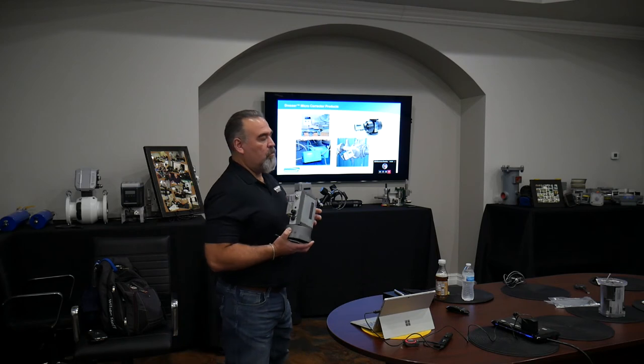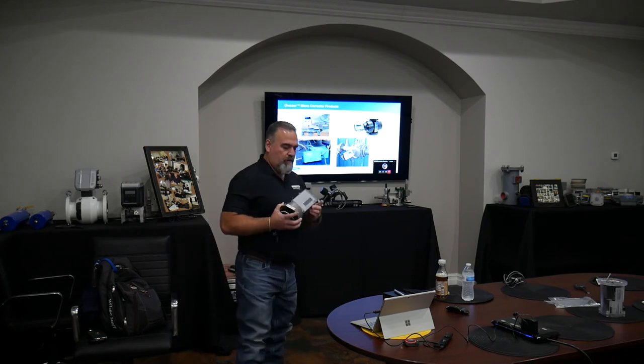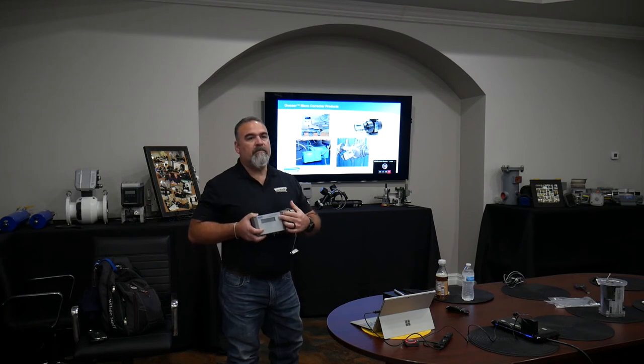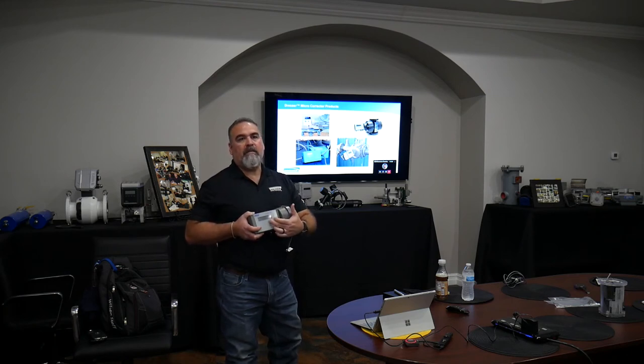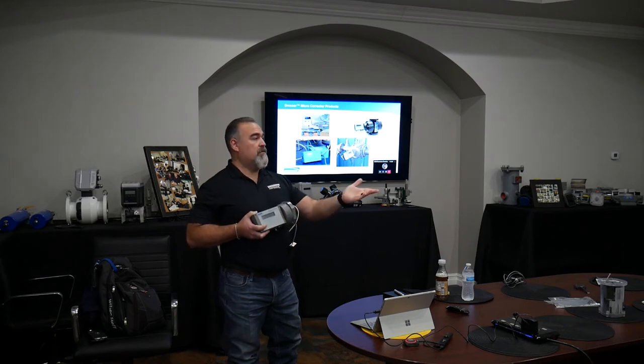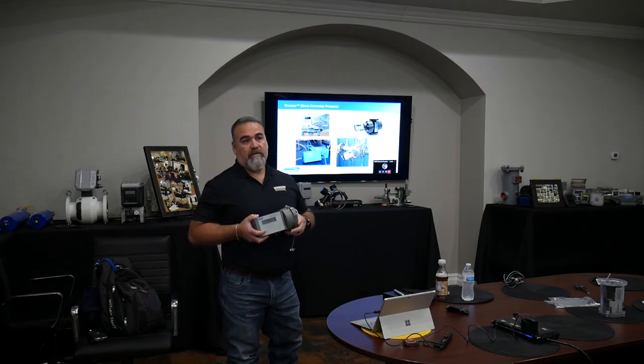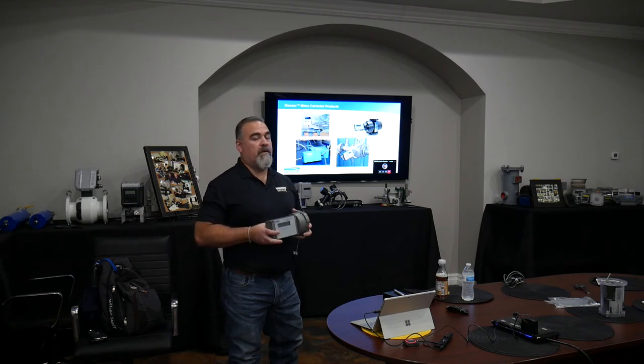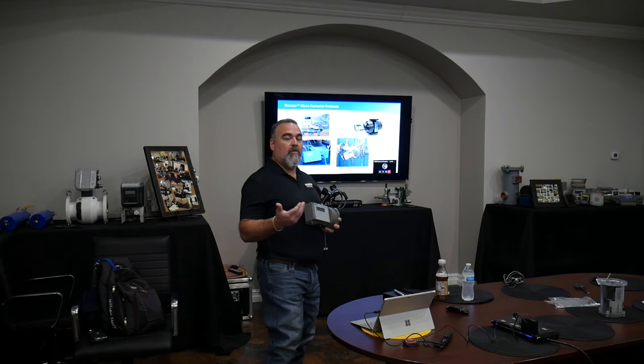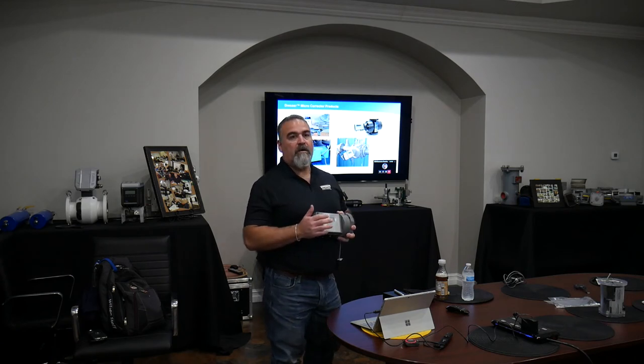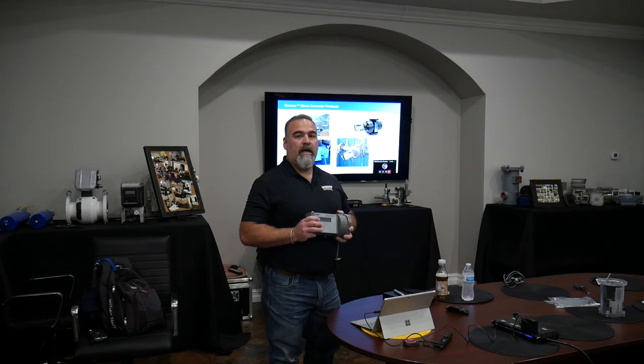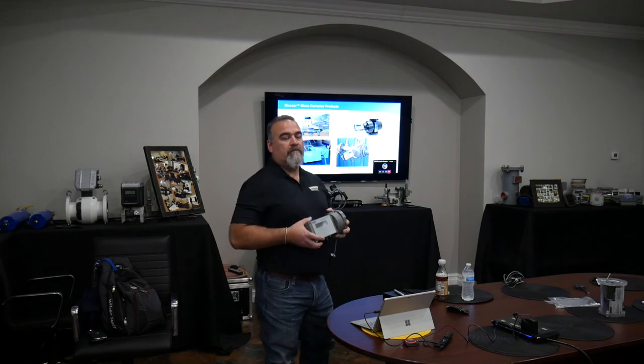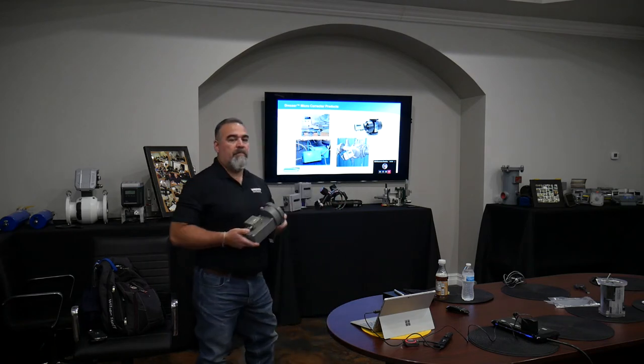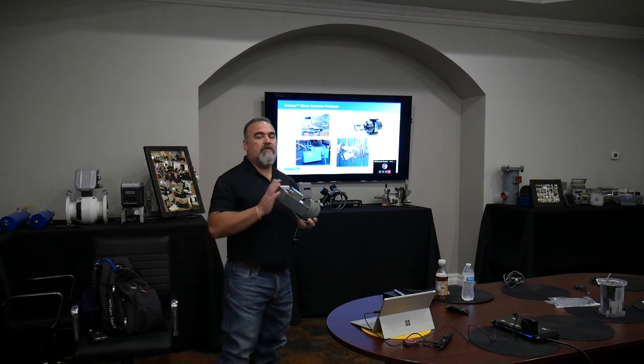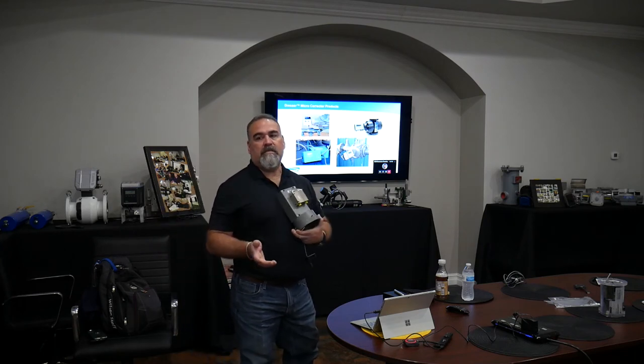So you're able to walk up to the meter, push the button, scroll through the screen, and see what the last DP was. A lot of the sites we go to have oversized meters, so in summer it's hard to see the DP when you come up to it. But right now, when it's cold and gas flow is going, we know they'll reach probably 30% of volume at that site, so this logs that volume. That's the neat thing about the DP corrector—it monitors the health of the meter, not the accuracy, the health.